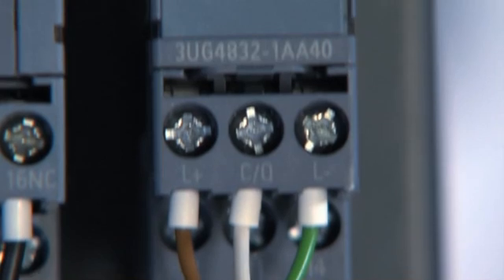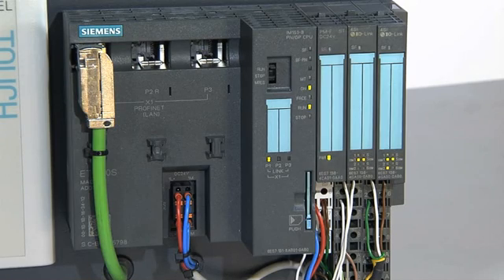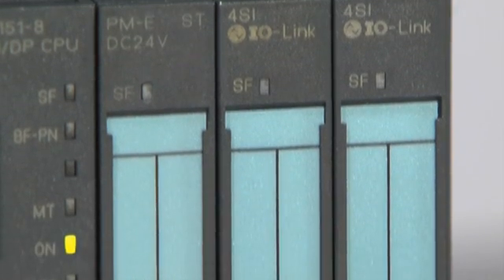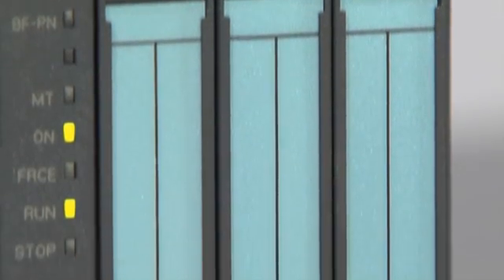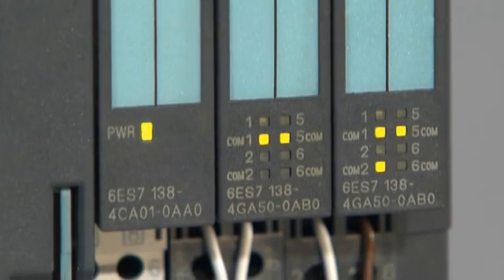The 3UG48 voltage monitoring relays are suitable, for example, for single-phase direct and alternating voltages. The IO-Link interface enables simple 3-wire connection to the higher-level controller. All measured values are transferred to the IO-Link master, further processed in the controller or shown on distributed displays such as HMI panels.